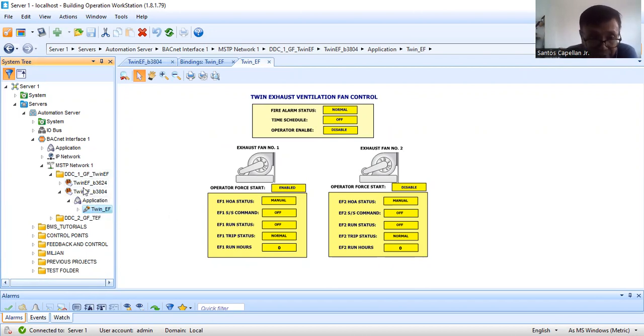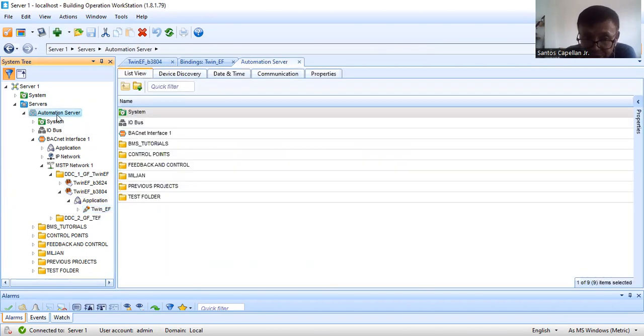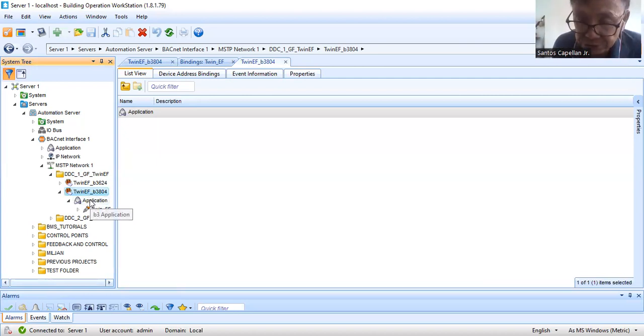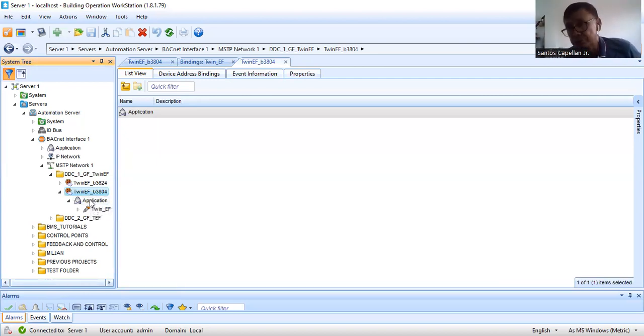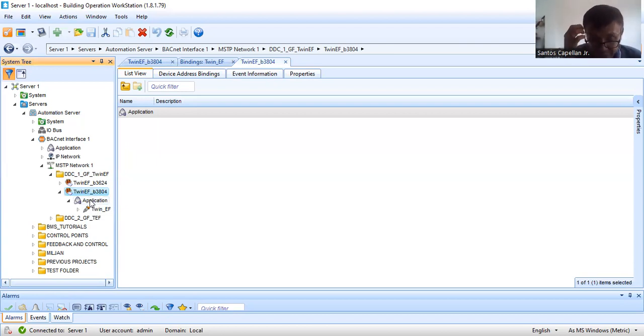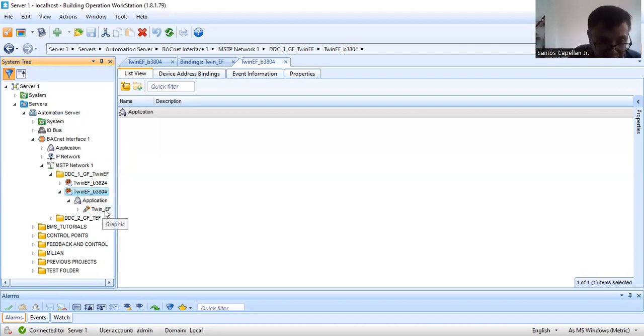As you can see, I created the object in the controller itself, because you can also create it in the automation server. I chose to create it in the BACnet controller — our B3804 — because I don't want to create too much traffic or too many objects in my automation server.